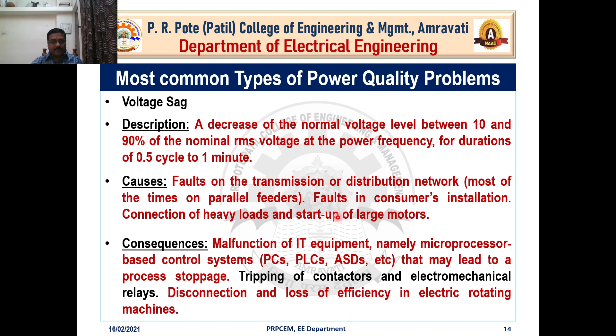The consequences of voltage sags are that some equipment, IT equipment, shows maloperation, namely microprocessor-based control systems, like those we observe in PCs, PLCs or adjustable speed drives, which may lead to a process stoppage. Or tripping of contactors and electromechanical relays also. That is also a consequence of voltage sags, as is disconnection and loss of efficiency in electric rotating machines because of the heating. So these are all the problems or consequences of voltage sag.